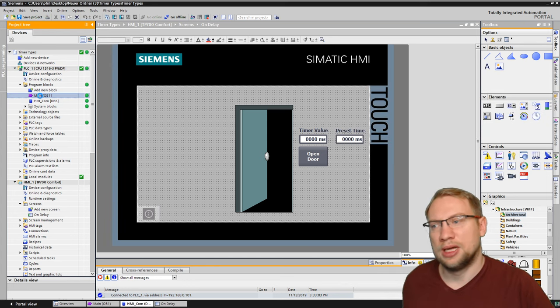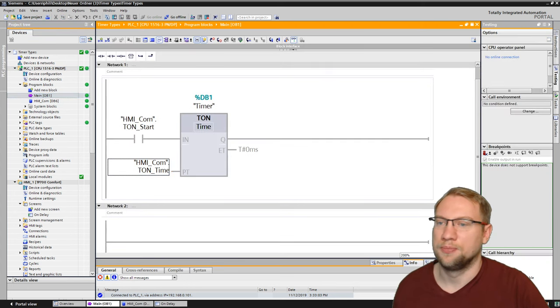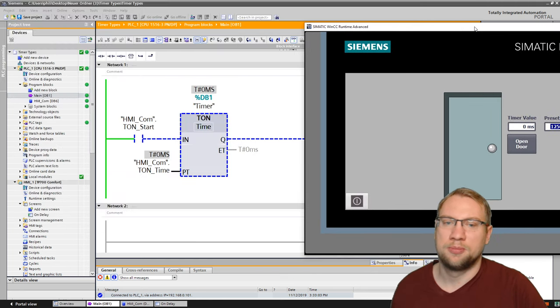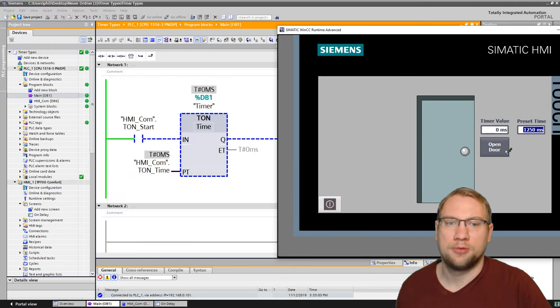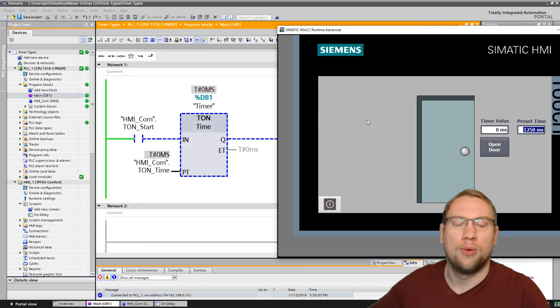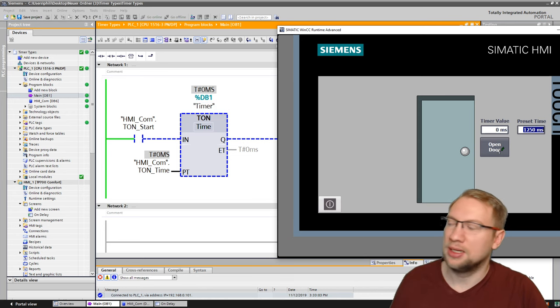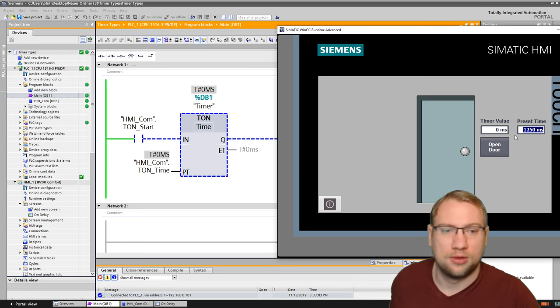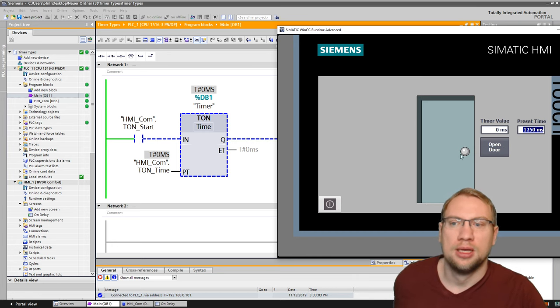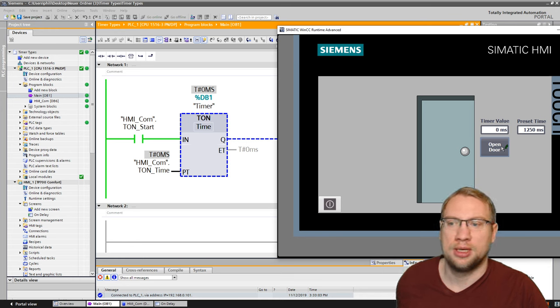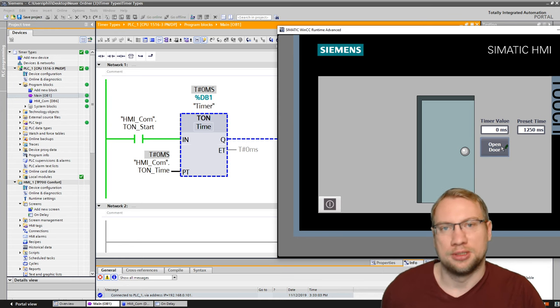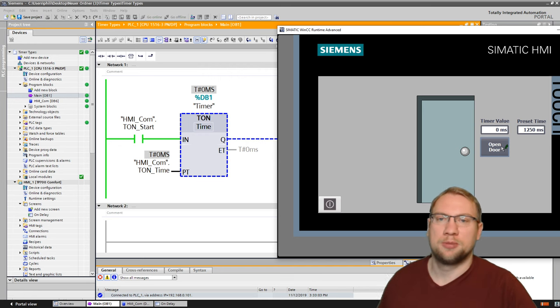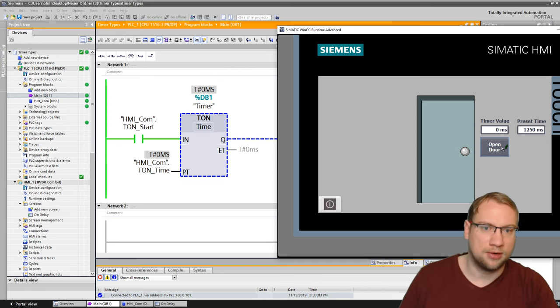So what happens now? I have my timer here. And when I press this button, this time up here should go up. And at reaching 1.25 seconds, or 1,250 milliseconds, the Q output should turn true. But you see that? I press it. Nothing happens.